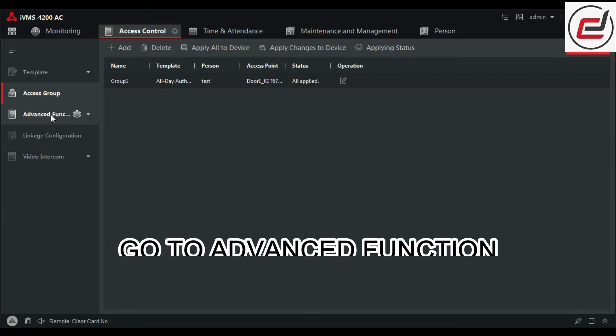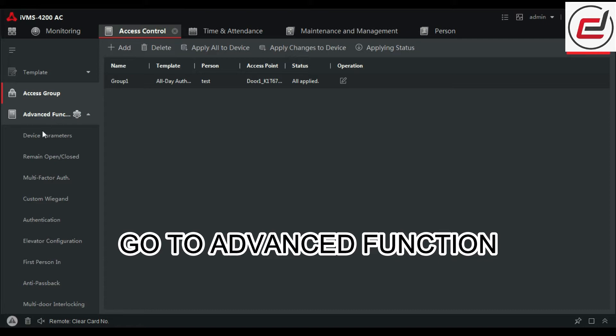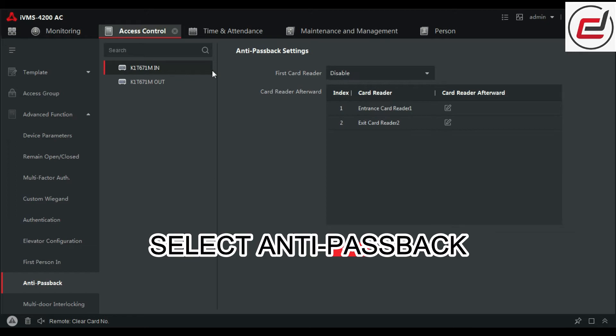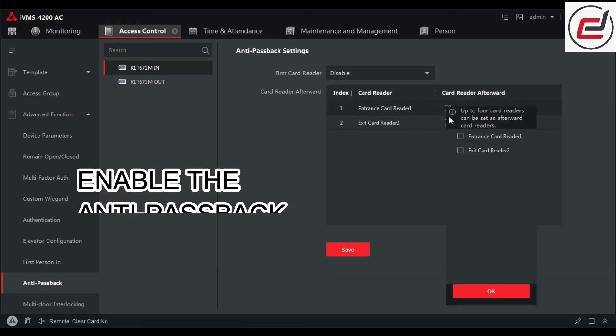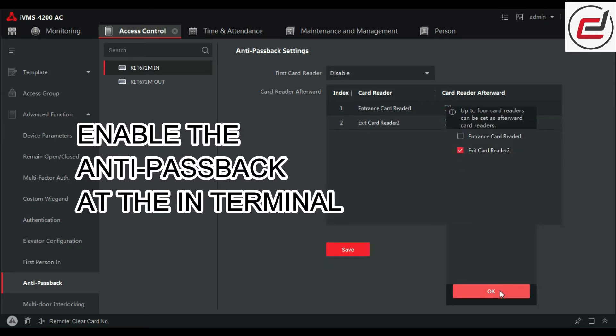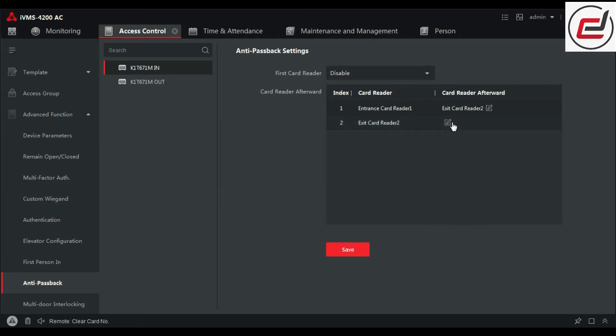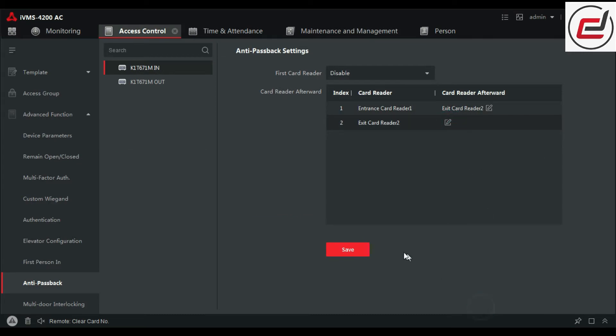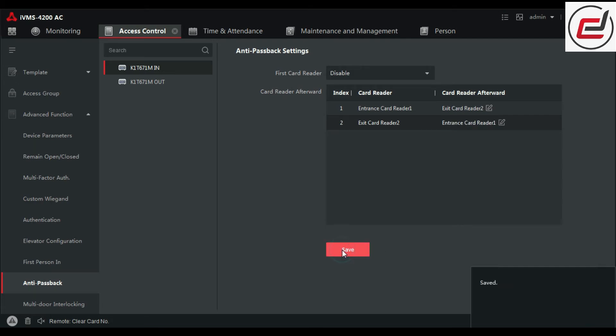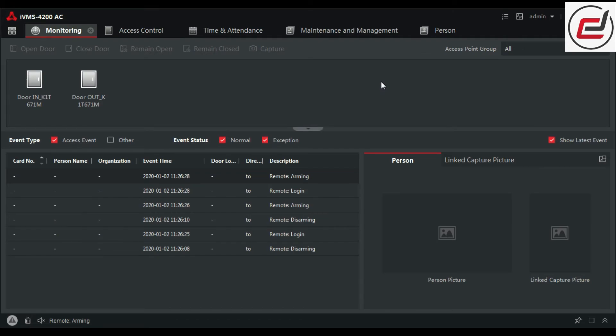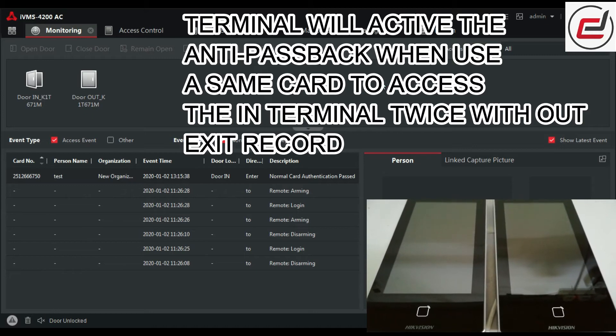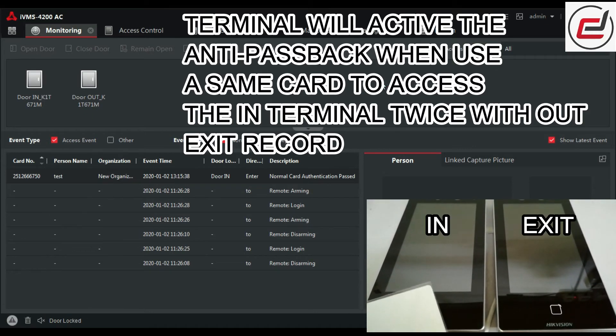Go to advanced function. Select anti-passback. Enable the anti-passback at the in-terminal. The terminal will activate the anti-passback when the same card is used to access the in-terminal twice without an exit record.